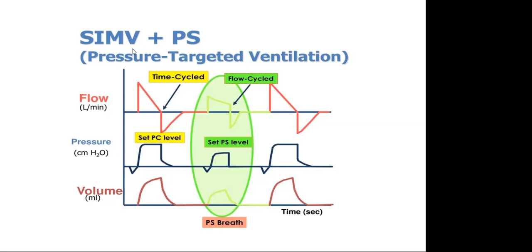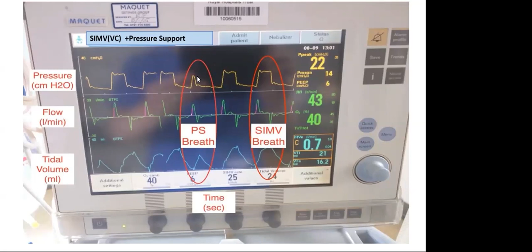The pressure support is mainly for your spontaneous breath. How much support you are giving, depending on that, you can set the pressure support level. Usually you will keep it a little lower than the pressure control level. So this is the common mode which we will see, and this is how it looks. Suppose this is the SIMV volume control with pressure support. You can see here tidal volume, rate, PEEP. So this is the SIMV breath. You can see here the pressure difference. And this is the spontaneous breath, which is pressure supported. So this is the SIMV breath and the pressure support breath.